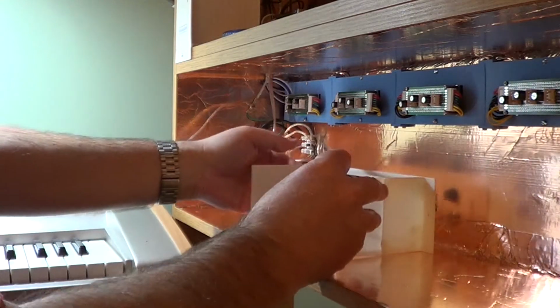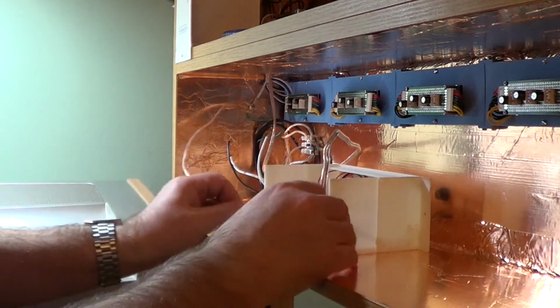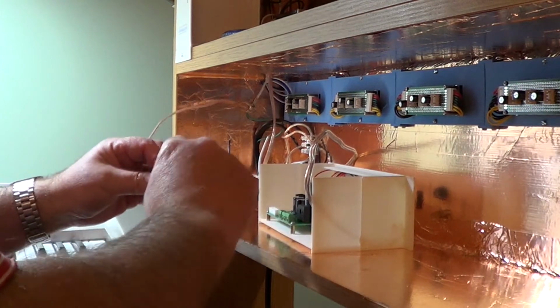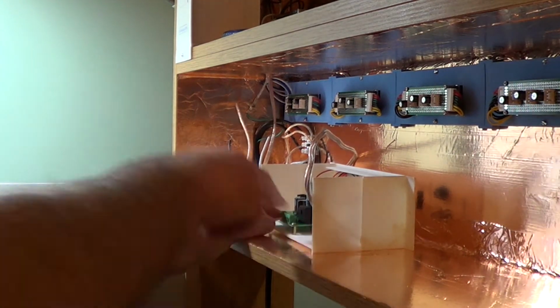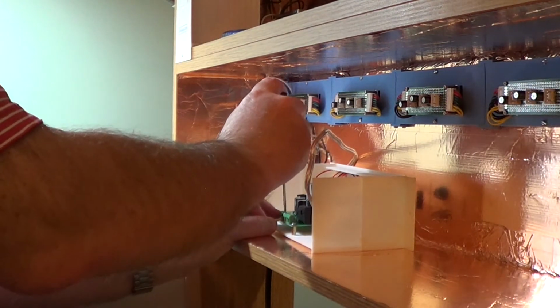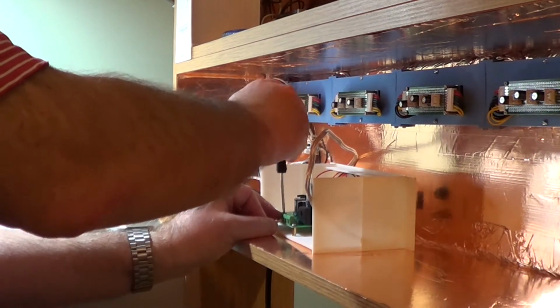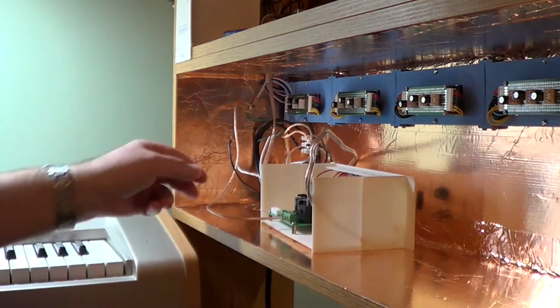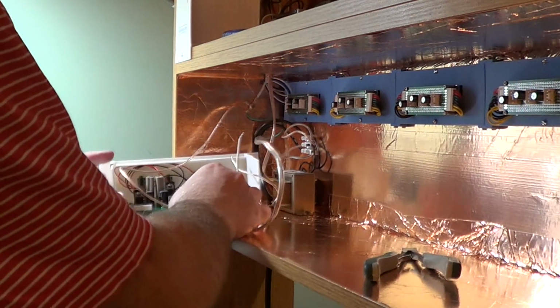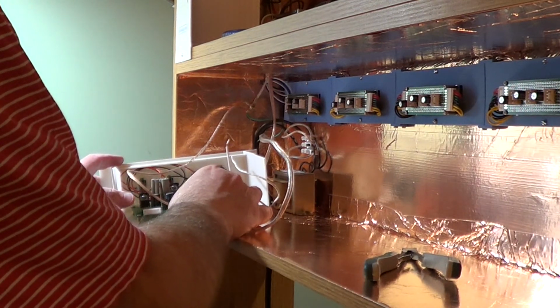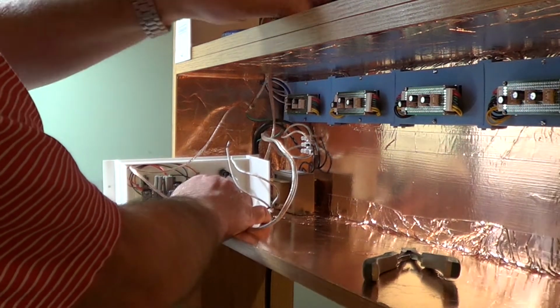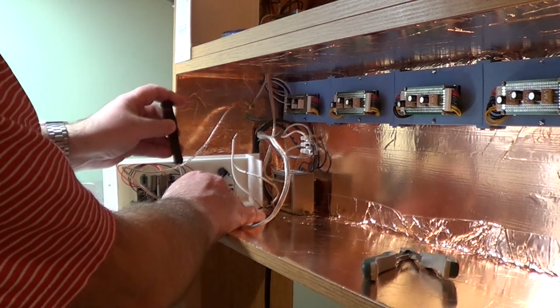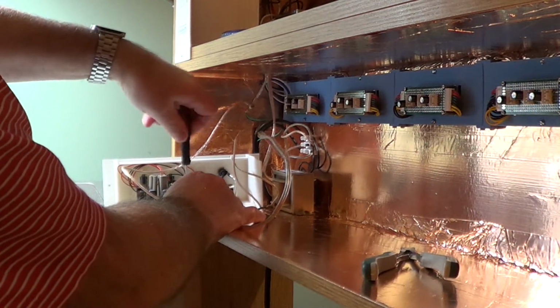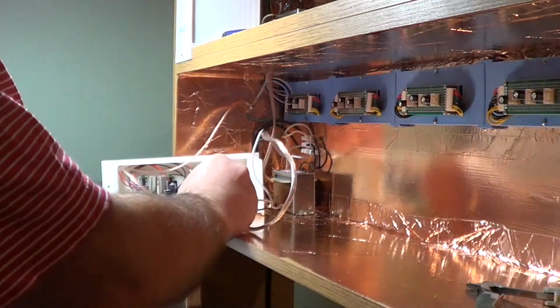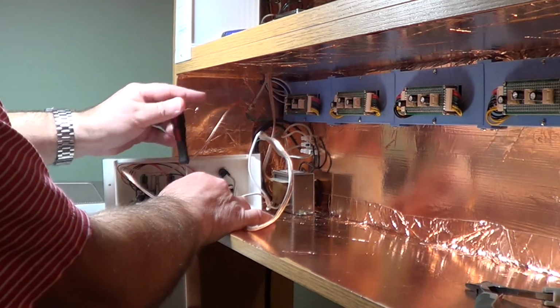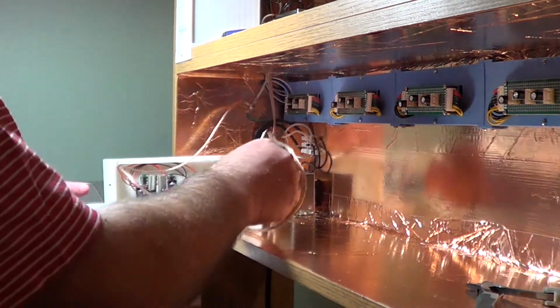Now the only thing left to do is connect the ground wire and the transformer wires to the main power module. Starting with the ground wire, and now the transformer. First the center of the secondary, which is basically the electrical ground of the low power circuits but also connected to the common ground, then the two white wires that carry the two 12 volt AC voltages.